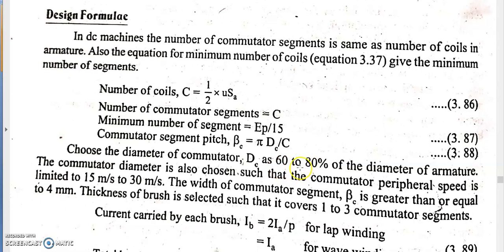The diameter of the commutator DC is taken as 60 to 80 percent of the armature diameter D. Since DC and the number of coils C are both known, we can calculate the commutator segment pitch.